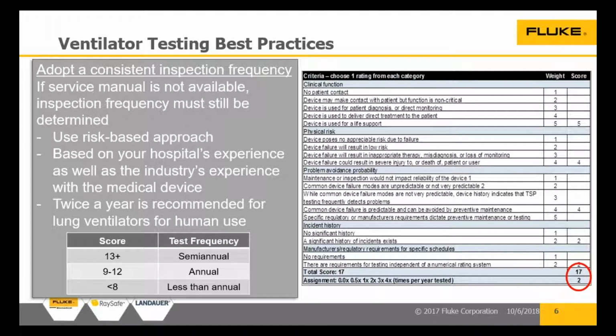Most of the time, it'll agree. In fact, up until about a year or two ago, I would have said for electrosurgery units, for example, absolutely it would agree every time. That matches up very well until Medtronic, because they know their design so well and they know the safety or the risk of their design and use so well, reduced their ESU inspection frequency to once per year.